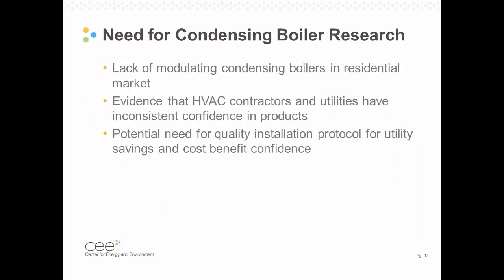So as we were getting going on starting this project, we were looking at what are the needs that we wanted to find out about residential condensing boilers through our research. And one of the things we noticed was that there was quite a lack of modulating condensing boilers in the residential market. So we often see condensing forced air furnaces being put in as replacements in residential homes, but much less so for boilers. So we wanted to look at why that was. There was some anecdotal evidence that HVAC contractors and utilities may have had inconsistent confidence with the performance of the condensing boilers, so some skepticism on their efficiency, and that we thought there might be an opportunity for a quality installation protocol to make sure that we're getting that condensation rate that we just talked about.